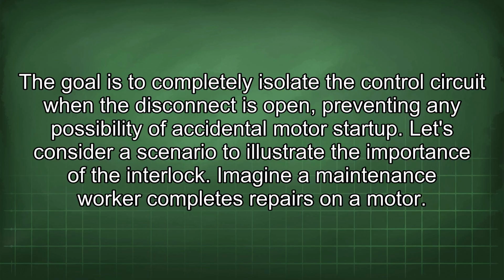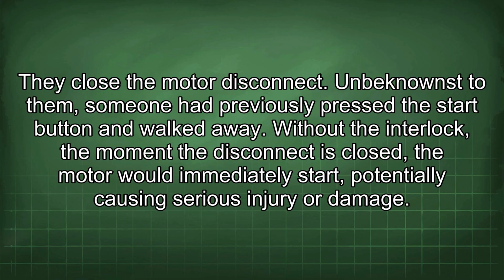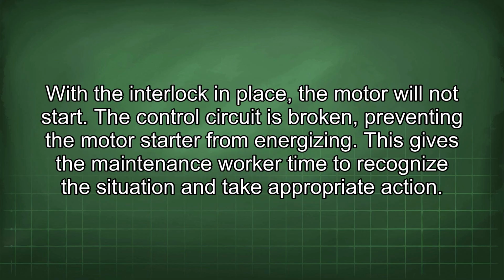Let's consider a scenario to illustrate the importance of the interlock. Imagine a maintenance worker completes repairs on a motor. They close the motor disconnect. Unbeknownst to them, someone had previously pressed the start button and walked away. Without the interlock, the moment the disconnect is closed, the motor would immediately start, potentially causing serious injury or damage. With the interlock in place, the motor will not start. The control circuit is broken, preventing the motor starter from energizing.